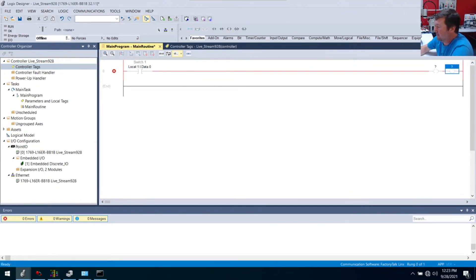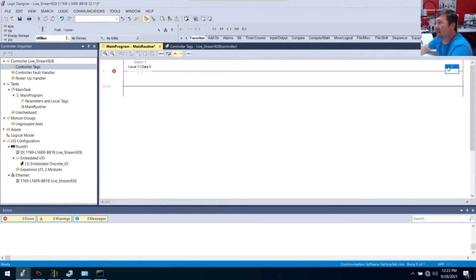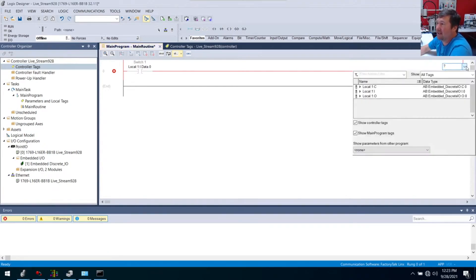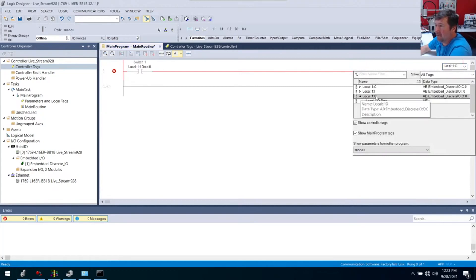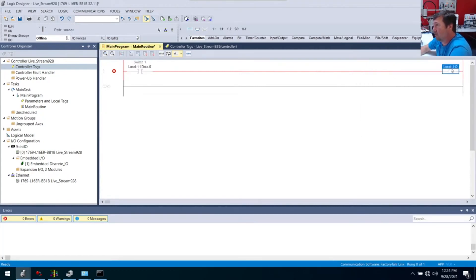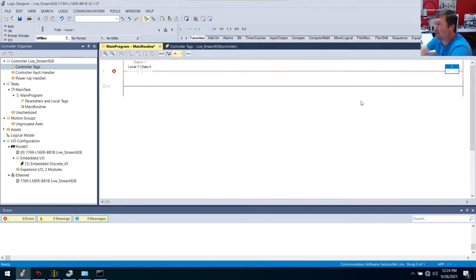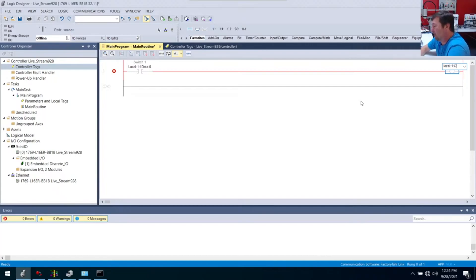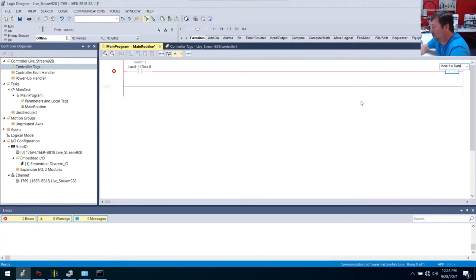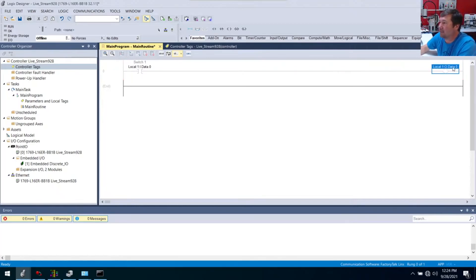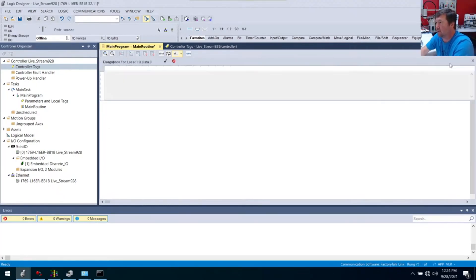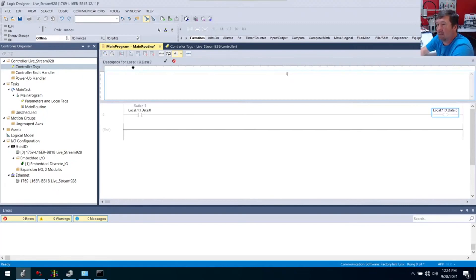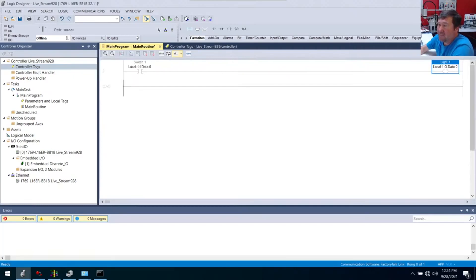Then we're going to need an output. I already had an output. I almost never use these dropdowns, but they're great when you're trying to find and start out. We can click here and navigate through this one. We know it's local. I can hit the L for local and then O. Notice this starts filling everything in. I want local:1:O, so I can backspace and hit O. Then I can hit the dot and I'm going to get what options are. We have data.0, so this is going to be output zero. While I didn't wire it to a light, I'm going to hit Control D and put light one.